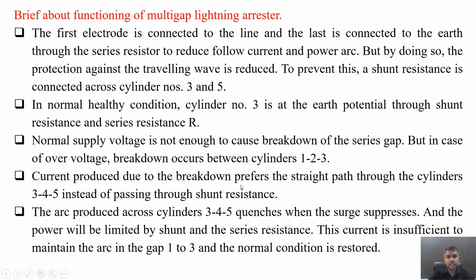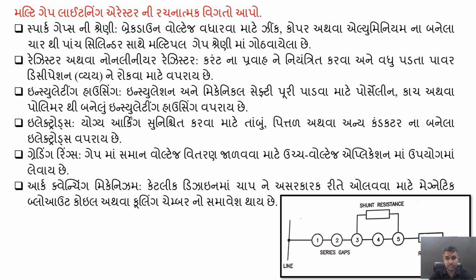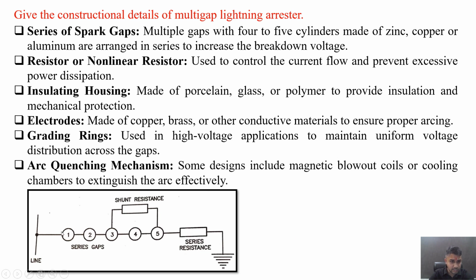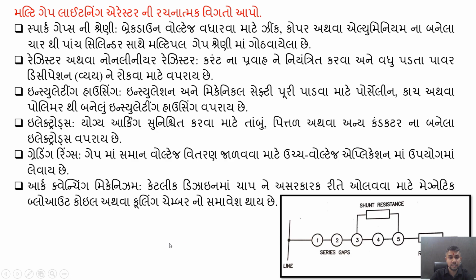So in normal healthy condition, cylinder number 3 is at the earth potential through shunt resistance and series resistance R. Normal supply voltage is not enough to cause breakdown of the series gap, but in case of over voltage, breakdown occurs between cylinder 1 to 3. Current produced due to the breakdown prefers the straight path through the cylinders 3, 4 and 5 instead of passing through the shunt resistance, because it offers a low resistance path to the arc. So current flows from line to earth with the help of this series resistance.